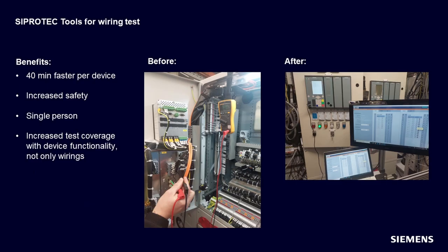To check the right cabling from the cubicle terminal to the device terminal, so far most of the time a continuity tester is used, where both the relay terminal and the cubicle terminal are contacted and tested. It is tested if they are connected via the cubicle wiring. This is a rather manual procedure and is time-consuming because both terminals must be identified. Moreover, this terminal search can lead to errors.